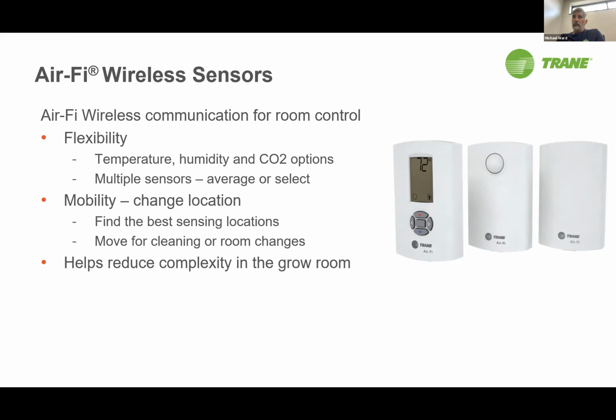So by doing so, we signed on with Trane to use their control system. What that enabled us to do is, between my head cultivator, myself, and my production manager, we have 3 locations where we can change any set point in any room at any time without even entering it. We also have displays outside of every room that we can use to control everything in the room, from the lighting, humidification, dehumidification, temperature, heat, and CO2, all from a stationary display outside the room, thus mitigating, my IPM manager would love this, the need to enter that room at all to adjust the temperature.